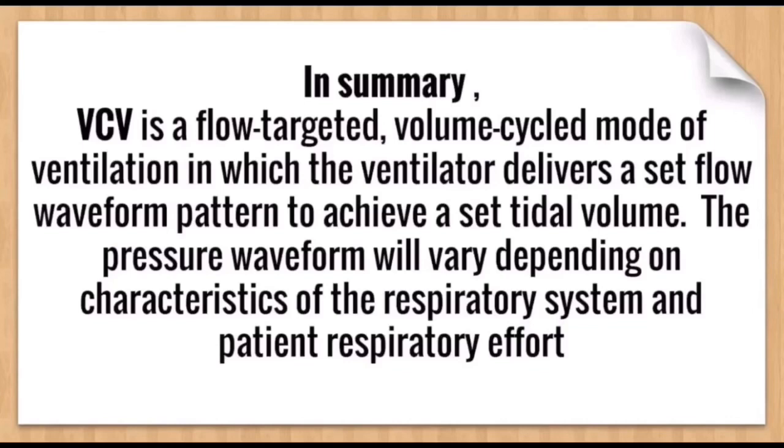So the only thing that can change is the pressure time graph. The flow and volume time graphs will not change because we have set the volume and the flow. When there is a change in the respiratory system or respiratory pattern, the only change you can see is in the pressure time graph in volume control ventilation.